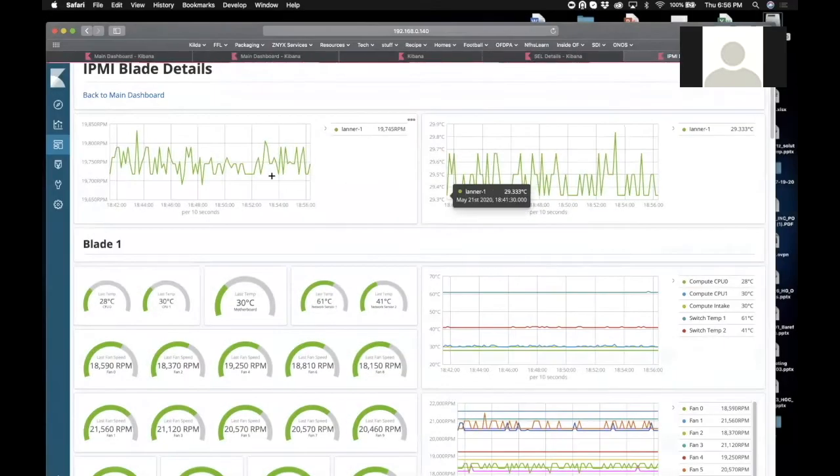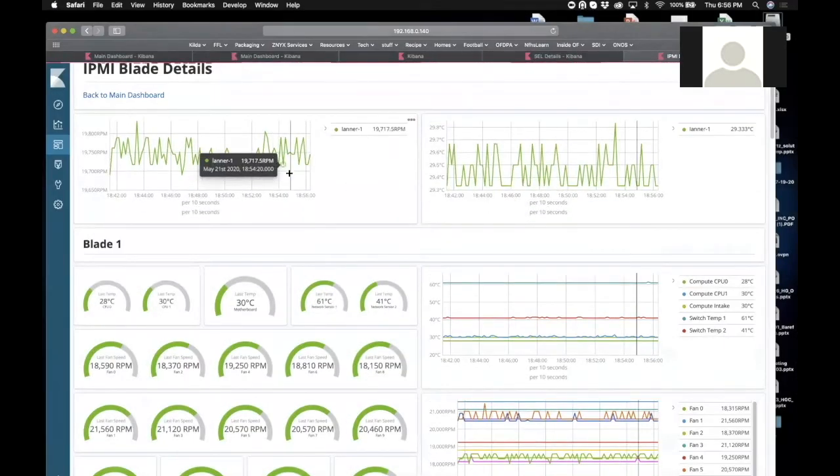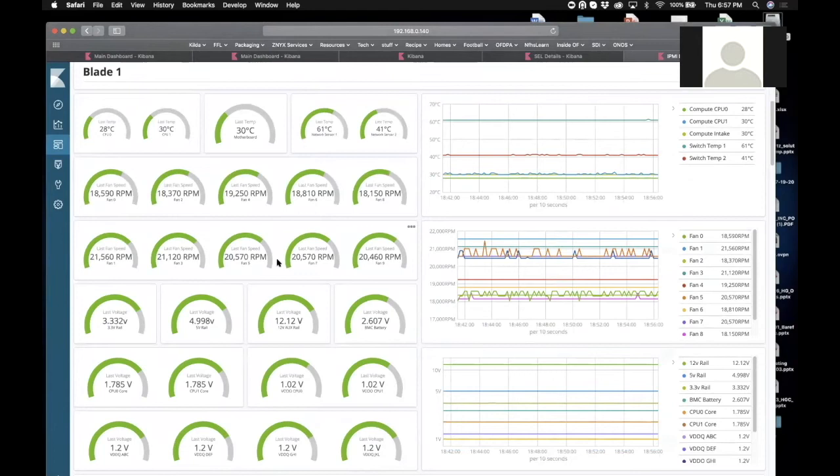And then we have the IPMI detail information where we can go in and we can take a look at all of the hardware subcomponents, the temperatures that's being recorded, the fan speeds being recorded. The two things that generate the most truck rolls are fans that die and we certainly don't want that because then you have overheating situations, and hard drives.